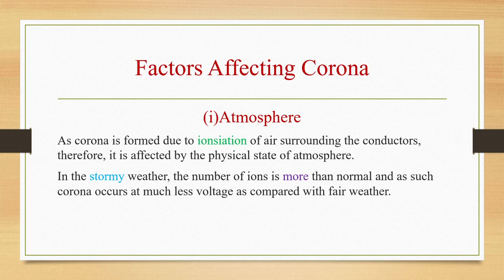So how is the atmosphere affecting corona? What we are telling here is that corona is formed because of ionization of air surrounding the conductor. So it is affected by how exactly the atmosphere is. If it is stormy weather, the number of ions will be more than the normal in the normal temperature. So in stormy weather, the number of ions will be more than those occurring in normal weather, and corona will occur. So we said earlier that it will occur at high voltage, but for stormy weather it may occur at much less voltage as compared with fair weather.